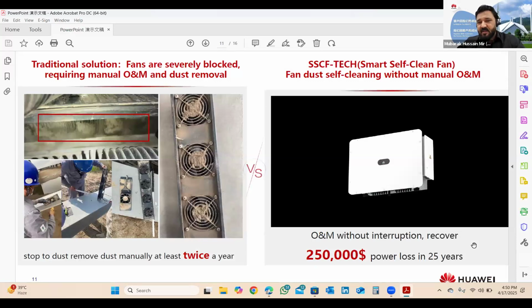Now this technology is available with mostly all the brands. And this is again one of the bigger issues the whole industry was facing. When you're installing the inverter in dustier areas, like the textile industry, cement industries, or sandy areas, the problem was the fan, which acts as a coolant for the inverter to perform well. The inverter fans were choking most of the time. So most of the inverters, especially Huawei ones, come with self-cleaning fans; the utility pro inverter 330 category inverters now already come with the self-cleaning fan concept. It automatically detects at a certain level that the fan is choked, so it automatically rotates the fan anti-clockwise for more than a minute. It cleans the fan and then starts going forward. So this is already integrated into the inverters.